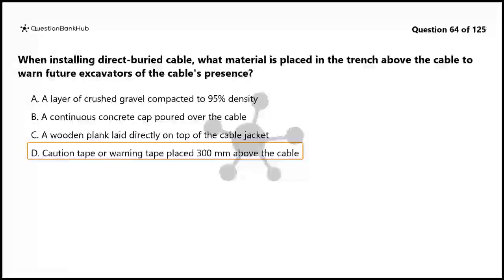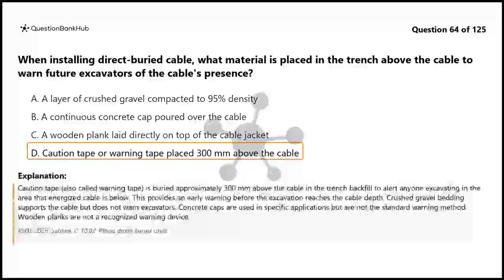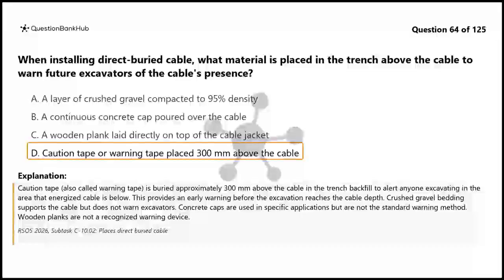The correct answer is D. Caution tape, also called warning tape, is buried approximately 300 mm above the cable in the trench backfill to alert anyone excavating in the area that energized cable is below. This provides an early warning before the excavation reaches the cable depth. Crushed gravel bedding supports the cable but does not warn excavators. Concrete caps are used in specific applications but are not the standard warning method. Wooden planks are not a recognized warning device.